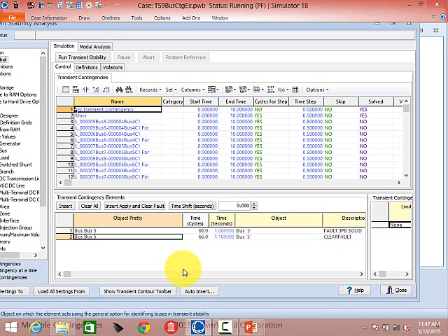So the design of it is, if you just think of the PowerFlow contingency analysis, the attempt is to make it the same thought process. Yeah, that's exactly right. That's the design, and it comes from the fact that before we start the transient run, we have stored everything. So we kind of put it over here. While we're running the stability runs, as we've shown you, we have the ability to take data from the stability run and put it back in our PowerFlow model. Then when you restore the reference, which takes place automatically during the multiple contingency runs, we start afresh.